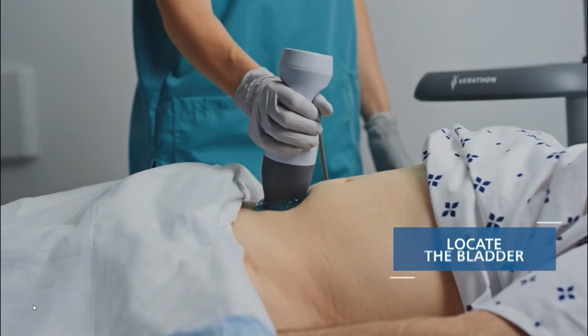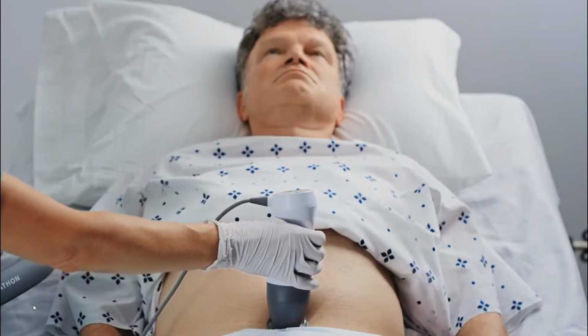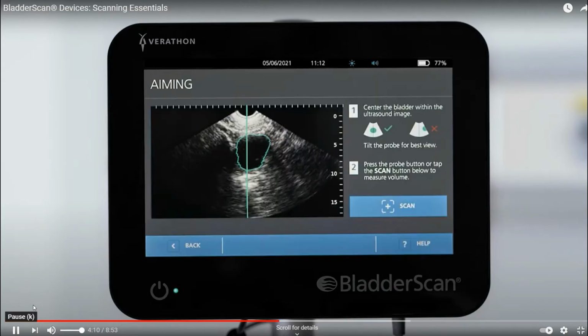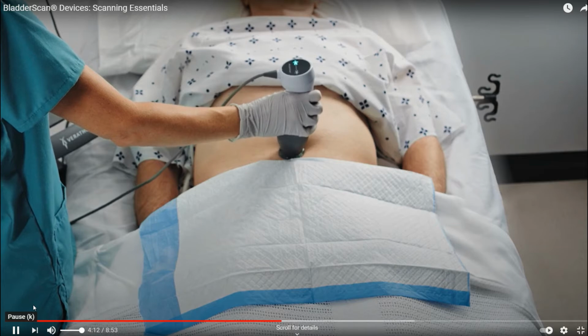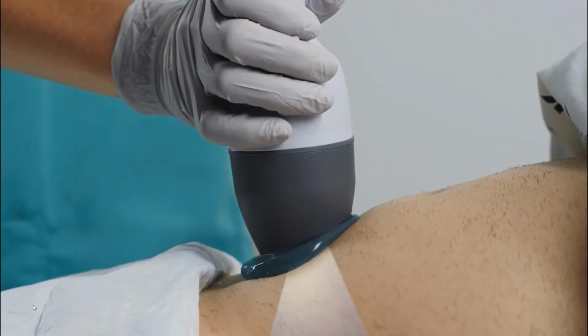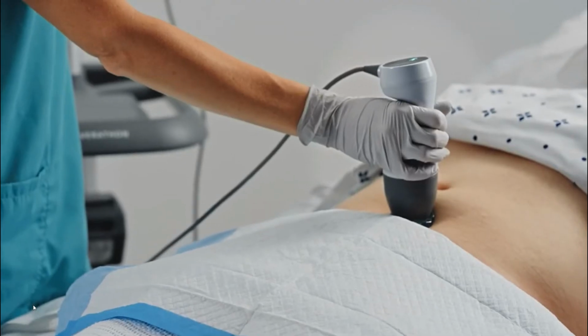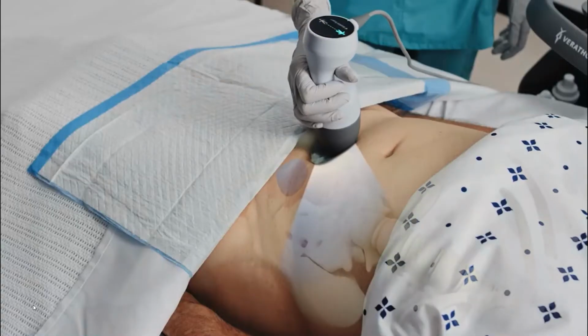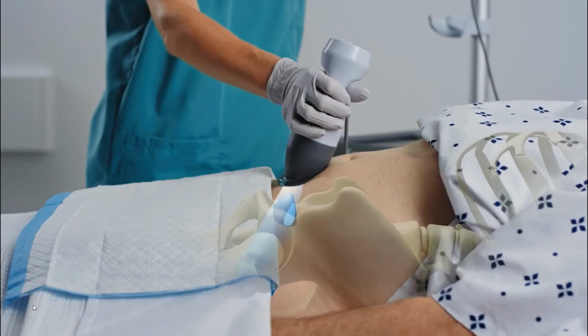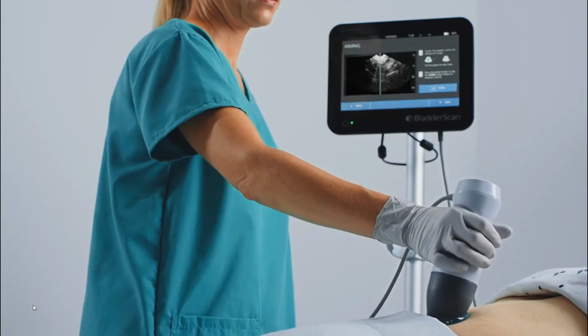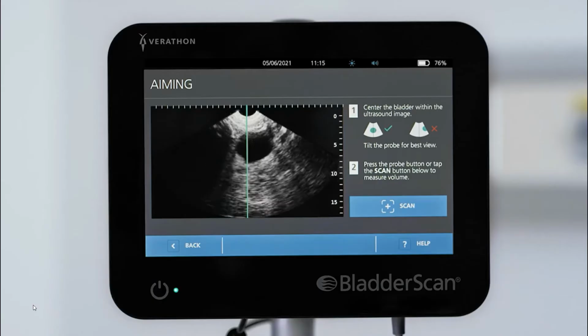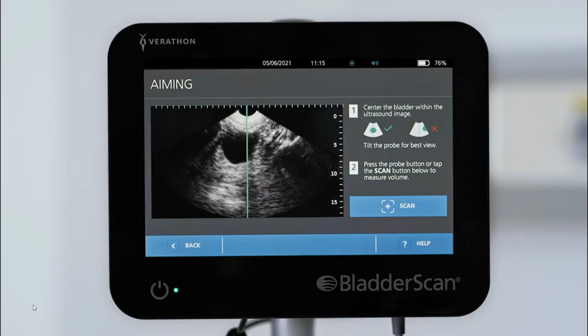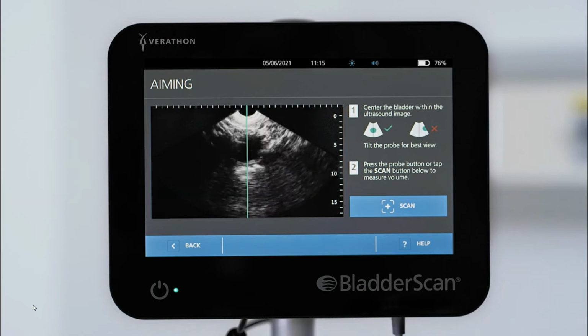The Bladder Scan System features pre-scan aiming to assist you in locating the bladder. Press the scan button on the probe or tap the screen to start aiming. Imagine the probe is a flashlight with light shining from the tip and the beam penetrating into the body. From your starting target area on the abdomen, angle the probe so the beam shines downward toward the bladder. On the bladder scan screen, fluid in the urinary bladder appears black, while other solid tissue and organs appear gray.